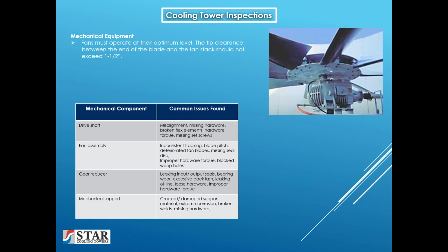Mechanical equipment. Fans must operate at their optimum level. The tip clearance between the end of the blade and the fan stack should not exceed 1.5 inches, because there will be a recirculation. The larger that distance is, the more recirculation or lost airflow will occur with the fan. The fan hub seal should be properly installed to prevent recirculation of the air. And this is an item that's particularly important to maintain the efficiency of the cooling tower.